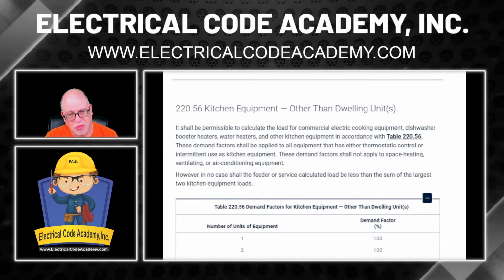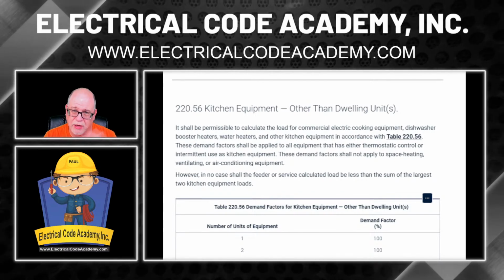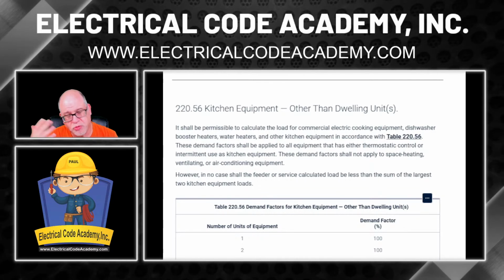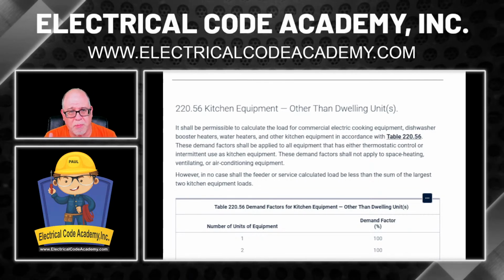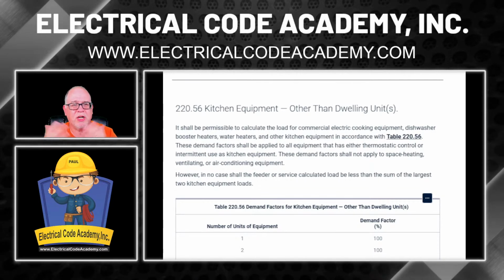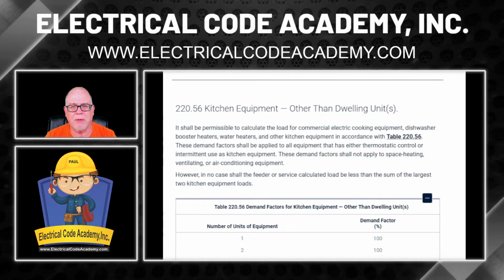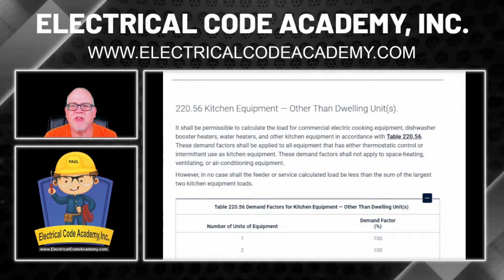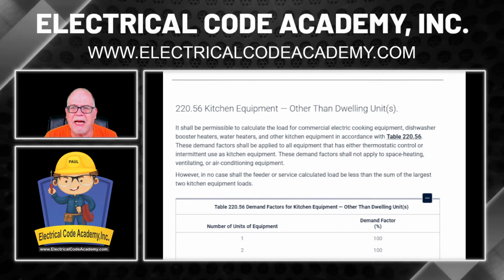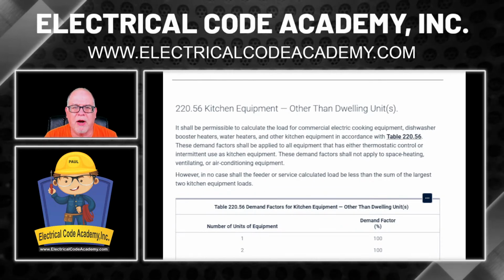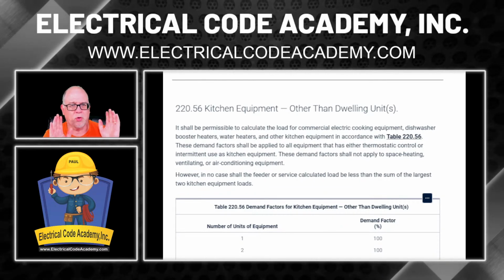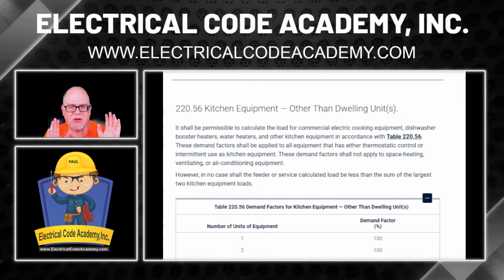Well, obviously, disposal's on when you need it. Water heater is going to come on when it's needed. Booster heater is going to come on when it's needed, but that's also probably thermostatically controlled. So we're good with all these pieces of equipment. It also says these demand factors shall not apply to space heating, ventilating, or air conditioning equipment. Yeah, because we got our own rules for that. So not going to have anything to do with that.